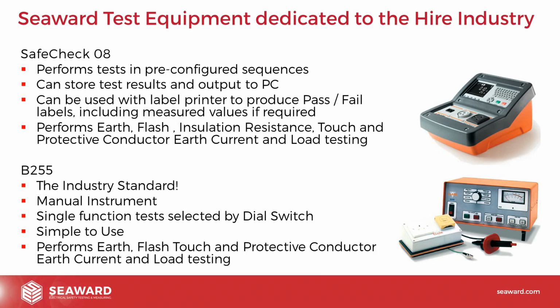In terms of test capabilities, it will perform the earth bond test, the flash test, the insulation resistance, the touch and protective conductor current test that we spoke about today, along with load testing.